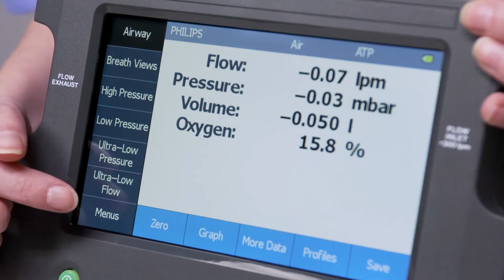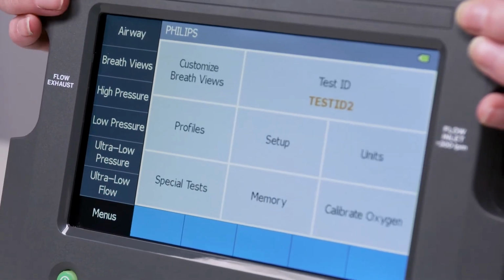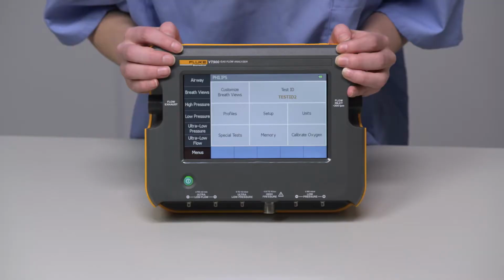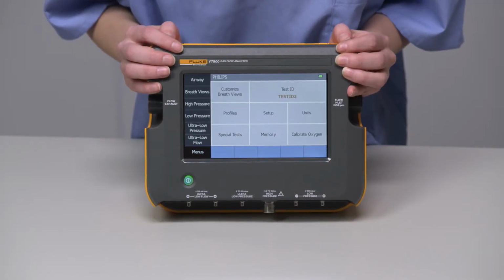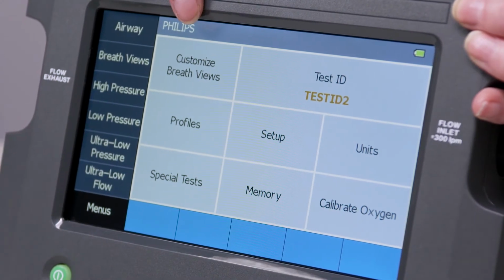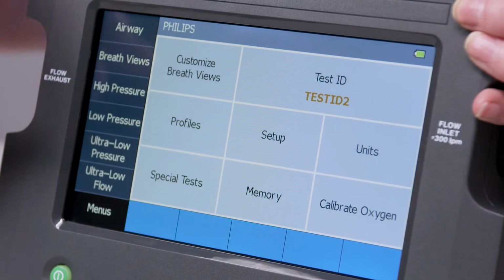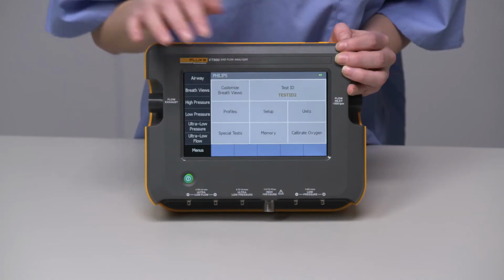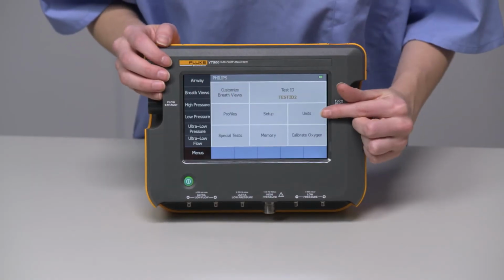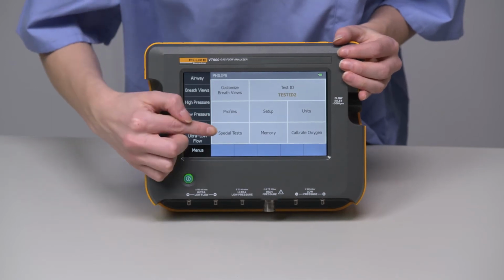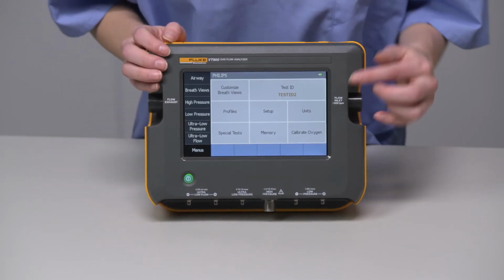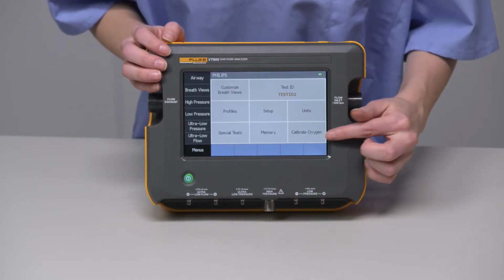Press the Menus option on the bottom left of the screen. Here is where you set up your device for testing and configure your testing preferences. On the Menus screen, you'll find the customization of breath views option, your test IDs, your saved profiles, device setup, change units of measurement, perform special tests, see saved data, and calibrate the oxygen sensor.